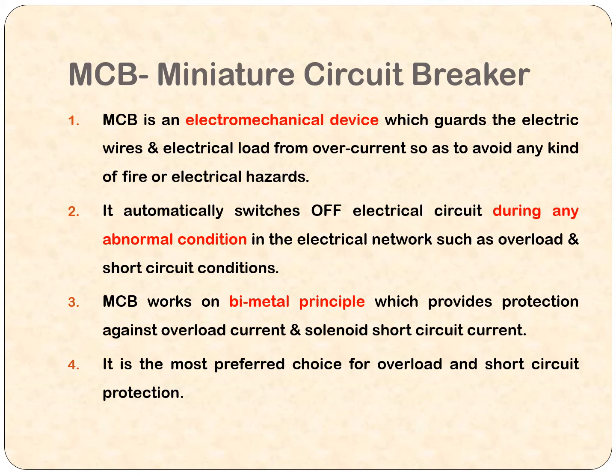What is there inside an MCB? It is nothing but a bimetallic strip. Bimetallic strip means it has two different metals which have different expansion rates. So when current heats up the two metals together, one metal will expand at one rate and the other will expand at another rate. So it causes a displacement, and that displacement is used as a switch to make the protection circuit come into the picture. That is, it will take switch-off action. So it is mostly the preferred choice for overcurrent and short circuit protection.